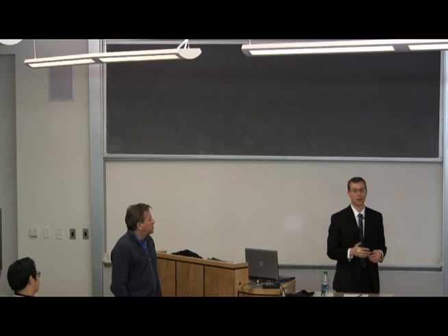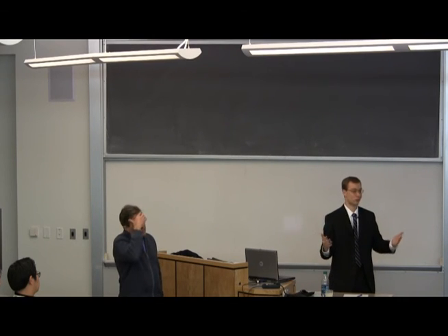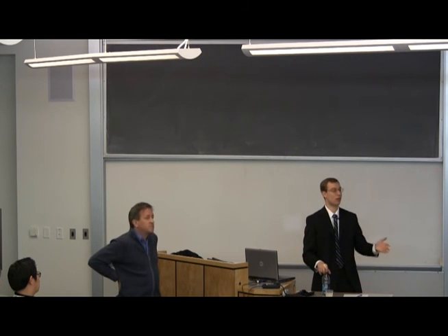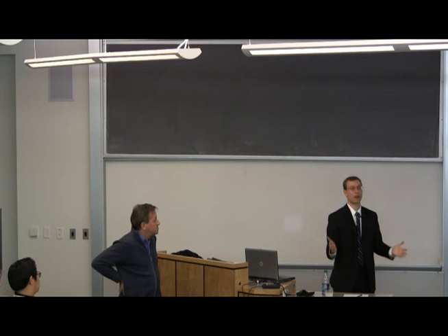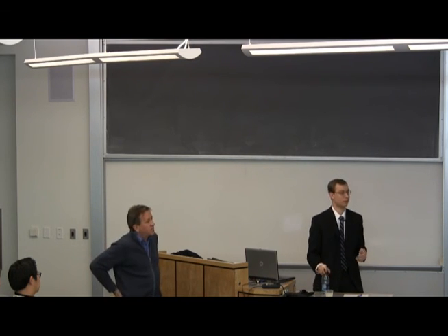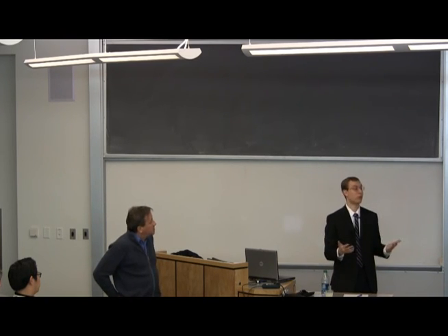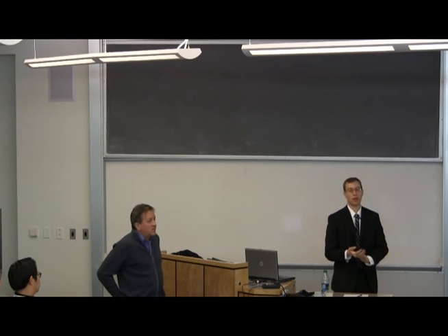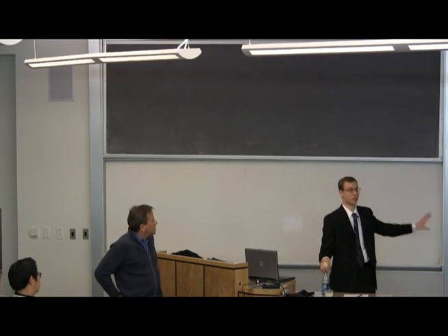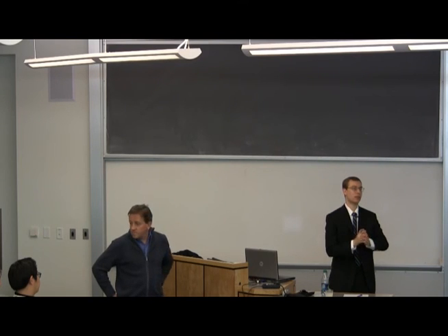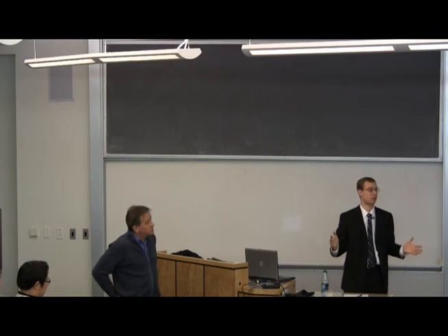If there's 40,000 lines, there's 40,000 potential loss-of-one-line contingencies. And when you start increasing the number, if two lines can go down at once, now you increase combinatorically the number of possible contingencies that you need to analyze. So the way things happen now is somebody with a lot of knowledge of the system. But that's another area that I haven't specifically addressed in this talk, but is certainly deserving of future research: can we look at different ways to break this huge set of possible contingencies down?